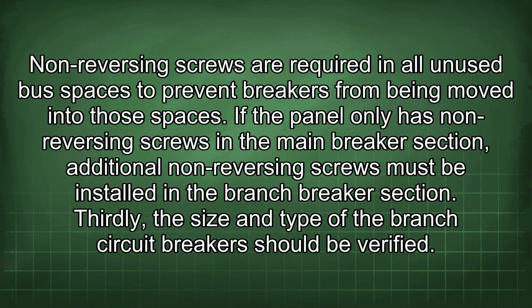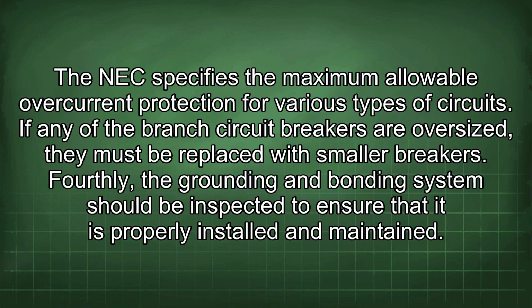Non-reversing screws are required in all unused bus spaces to prevent breakers from being moved into those spaces. If the panel only has non-reversing screws in the main breaker section, additional non-reversing screws must be installed in the branch breaker section. Thirdly, the size and type of the branch circuit breaker should be verified. The NEC specifies the maximum allowable overcurrent protection for various types of circuits. If any of the branch circuit breakers are oversized, they must be replaced with smaller breakers.